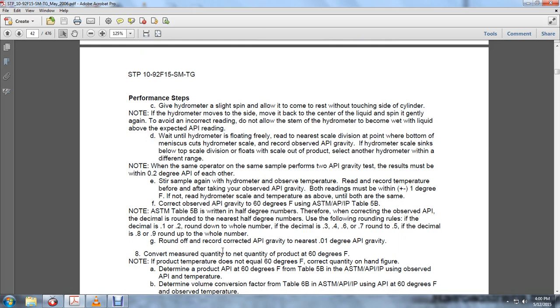Do not allow the stem of the hydrometer to become wet above the level of the liquid. Wait until the hydrometer is floating, and read the scale at the bottom of the meniscus. Record the API gravity. If the hydrometer scale sinks below the top scale division of the product, select another hydrometer with a different range. Note: when the same operator samples and performs the API gravity test, the results must be within 0.2 degrees API of each other. Stir the sample, observe and record the temperature reading, and take the observed API gravity. Both readings must be within 1 degree. If not, repeat until both are the same.